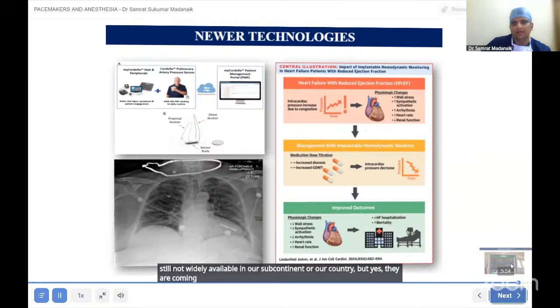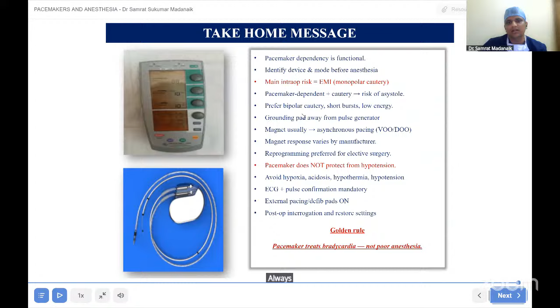So my take-home message is, remember, pacemaker dependency is functional. You have to identify the device and mode before anesthesia. The main intraoperative risk is monopolar cautery. You have to shift to bipolar cautery, and I have already told you how long the cautery burst should be. Always keep in mind that the grounding pad should be kept away from the pulse generator.